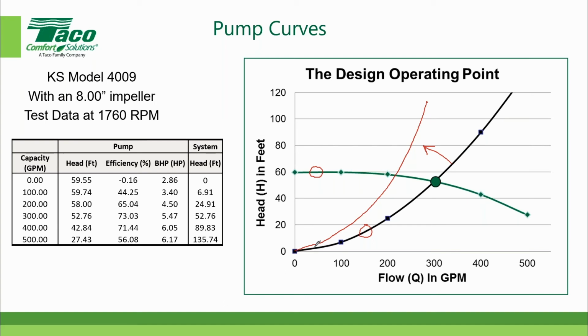If the pressure differential decreases, because the valves are opening, then the system curve bends downwards to the right, and we ride the pump curve in this direction. So if this was the system curve over here, let's kind of extend that little arrow up. Then this is where it would be riding on the pump curve. If the pressure was less, this is where it would ride on the pump curve.